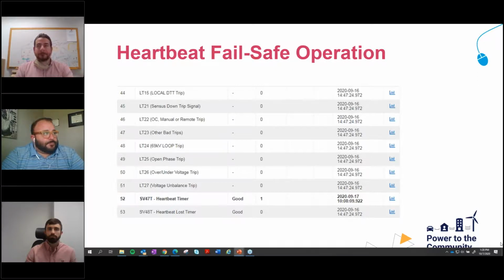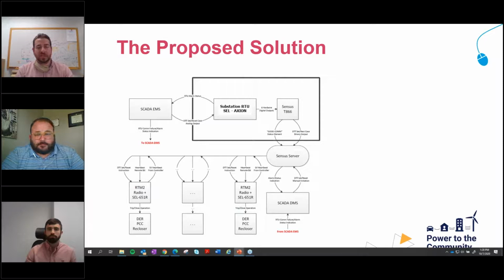Next slide. So again, a reiteration of the solution we're doing. The SCADA EMS system will be monitoring the transmission system, looking for abnormalities. It sends it out to an RTU there in the substation. The RTU sends it to the T866, this micro RTU. Just for clarity, the Axion is sending it out on digital outputs, and Sensus receives it on digital inputs. So there's no possibility of going backwards—inputs can't become outputs, and outputs can't become inputs.